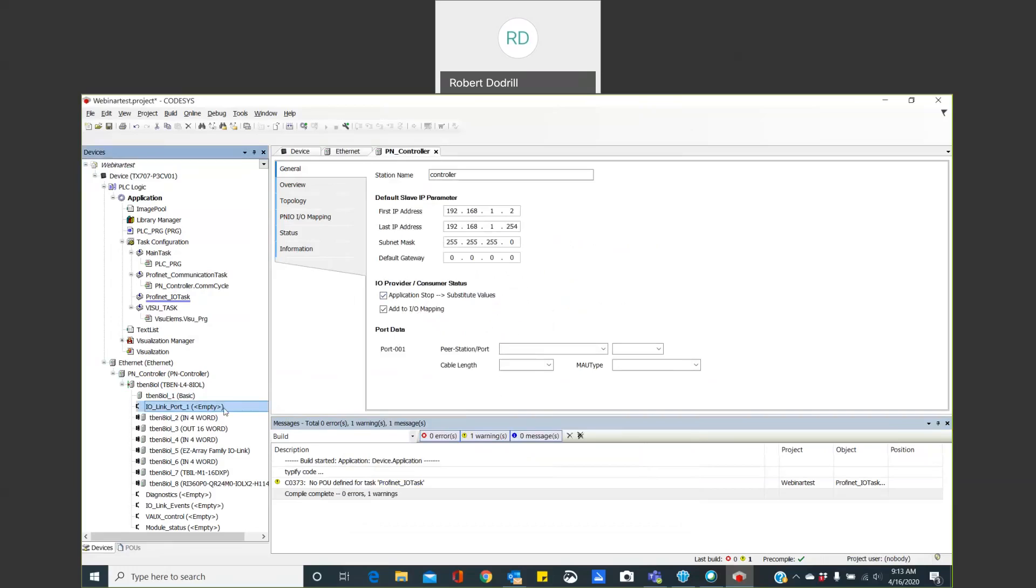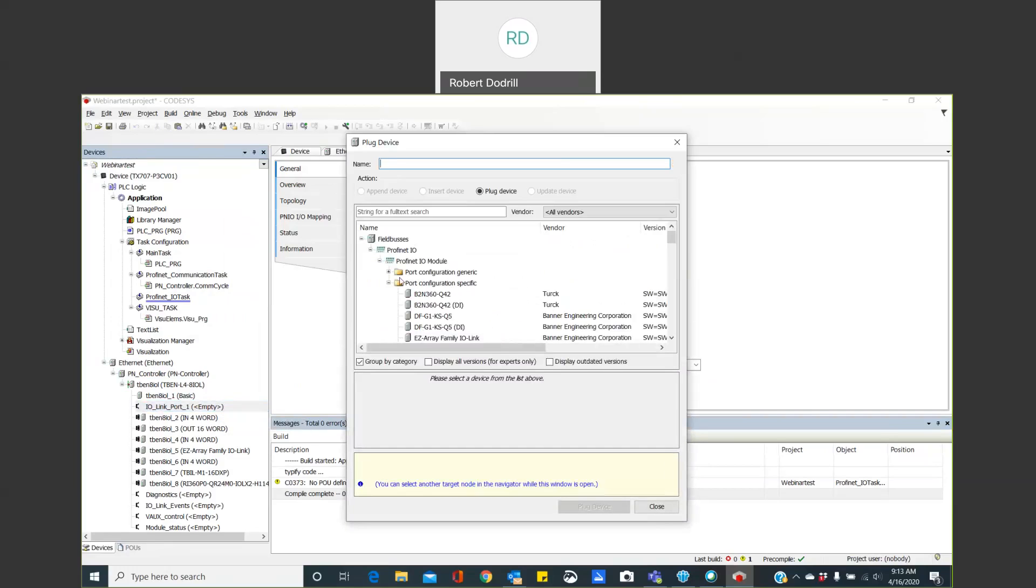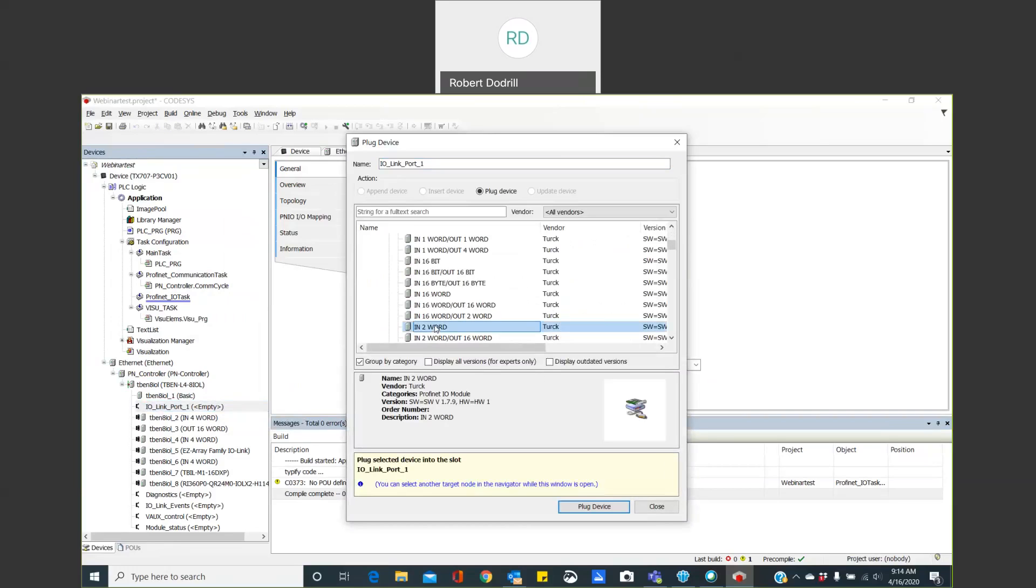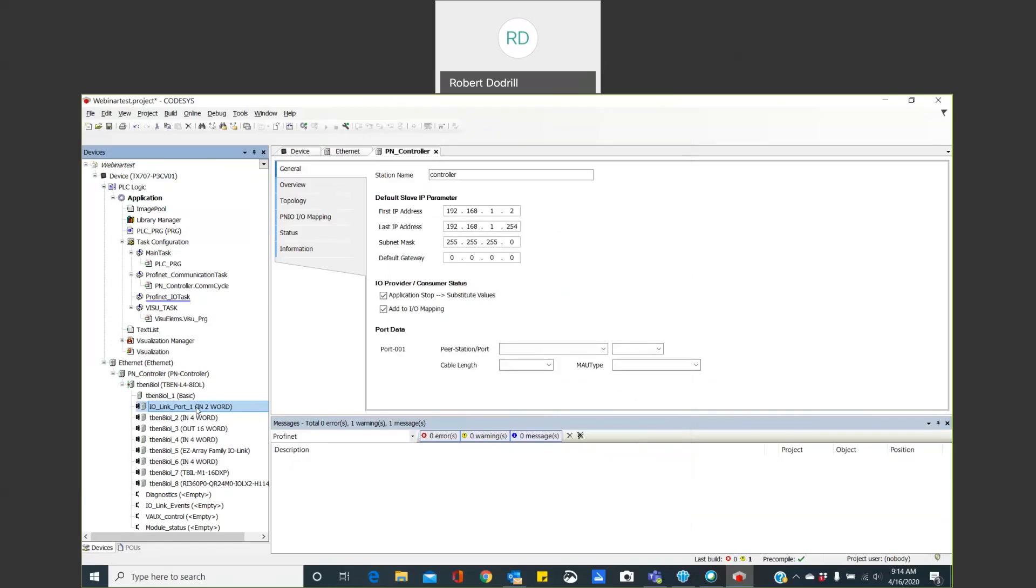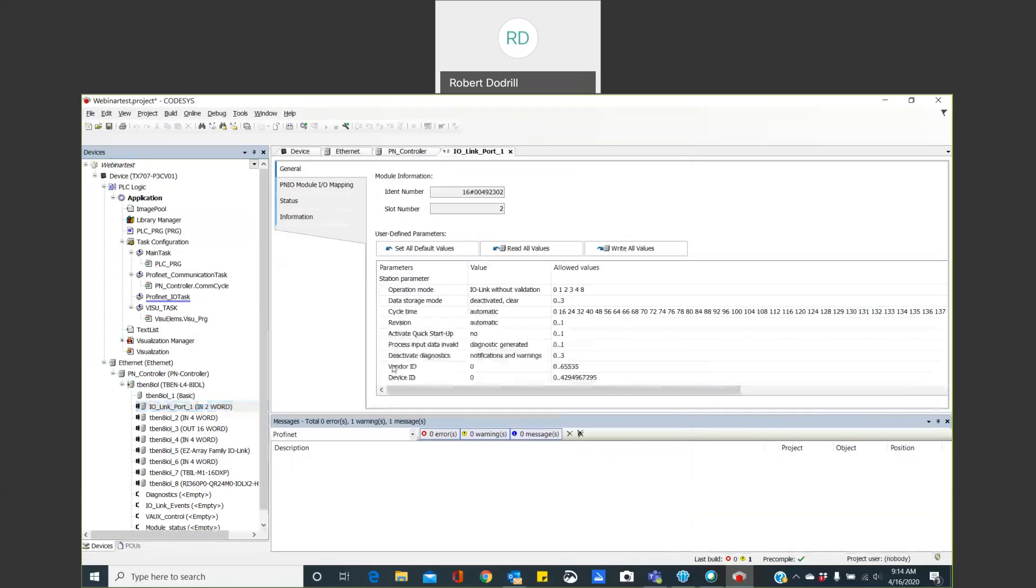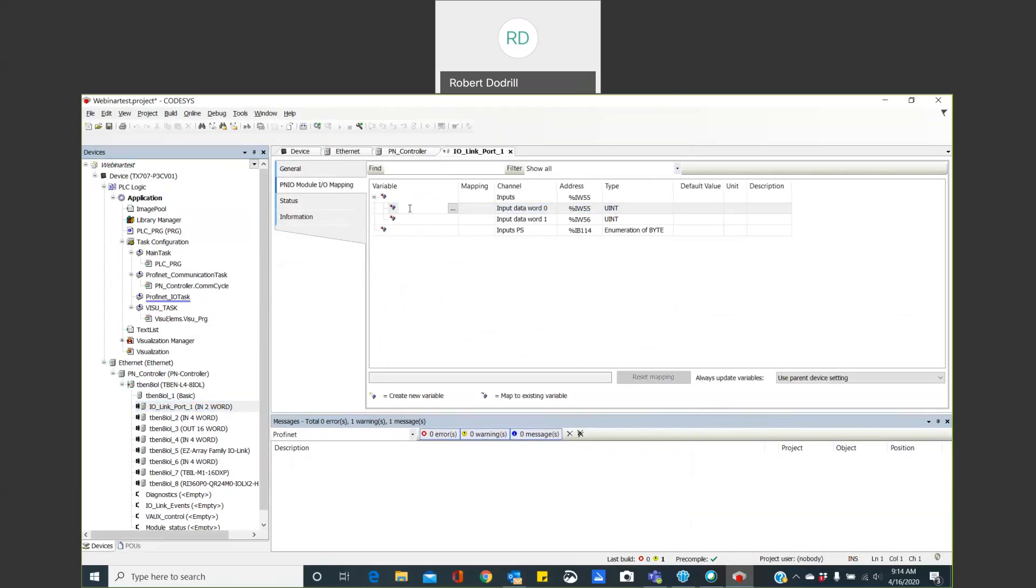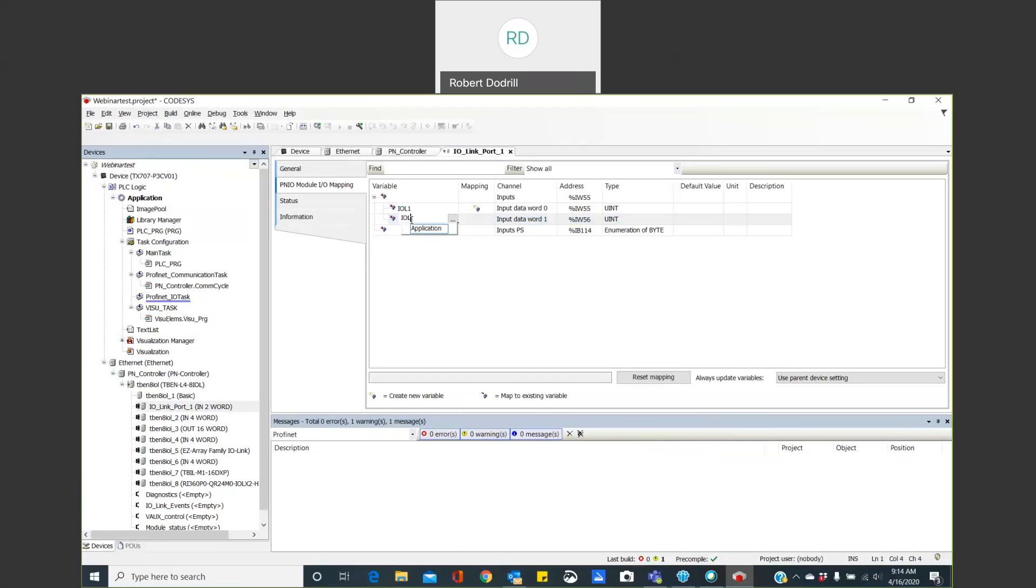Or if that's not in there, then I can right click. I can plug device and I can look at generic. So I already know that my device that I'm going to use, let's just say it's two words of input process data. So I'm going to click on that and I'm going to tell it to plug. So now I have my generic two word device in. I open that. It tells me now here's my parameterization menu. If I want to add some things here, if I want to make changes, here's my IO link. And then here is my mapping. And my mapping is where I can give things an address. So I'm going to give mine an alias and I'm just going to call it IOL1. I'm going to make this one IOL2.